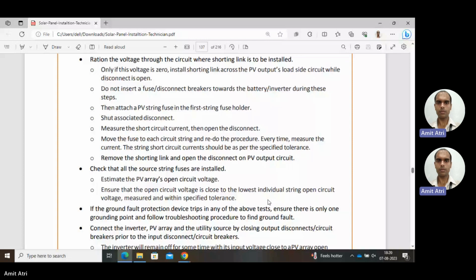So estimate the PV array's open circuit voltage. Ensure that the open circuit voltage is close to the lowest individual string open circuit voltage, because here the voltage level should be the same. Then only we are able to connect them. If the voltage in one individual string is different from another one, then our system won't work. A different voltage level. The net output we are obtaining will be at some other value, not what we are requiring. The measured values are within the specified tolerance. Okay, our value should be within the specified tolerance limit.